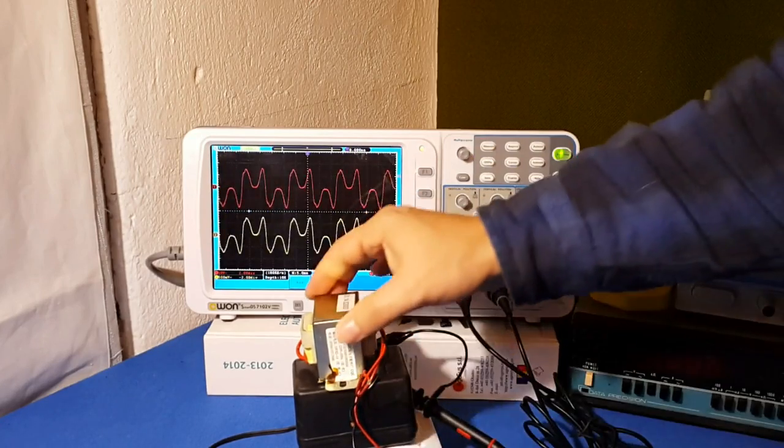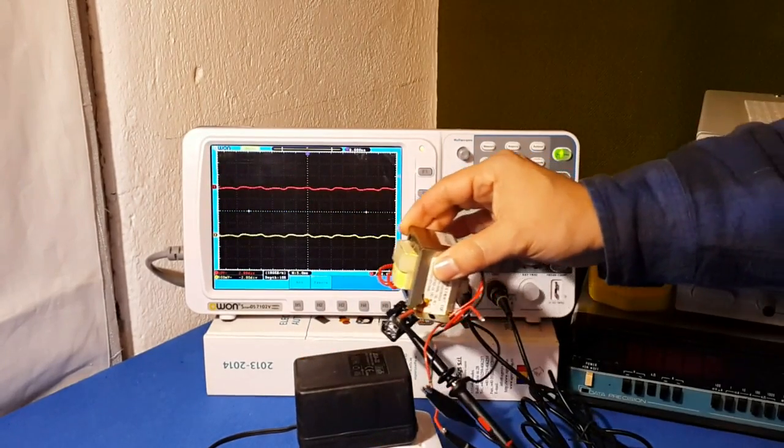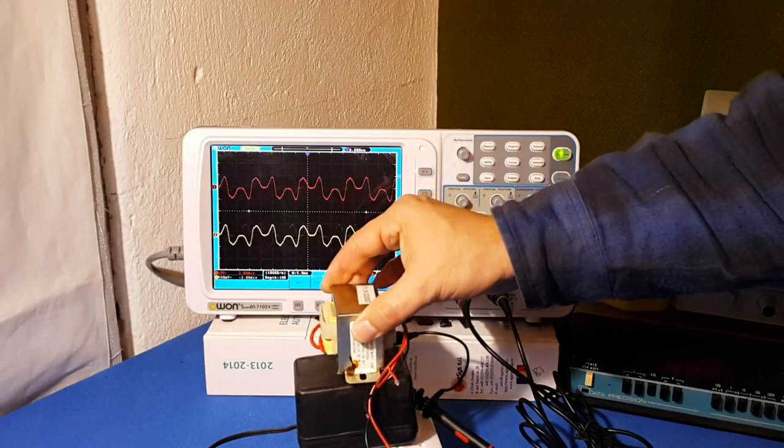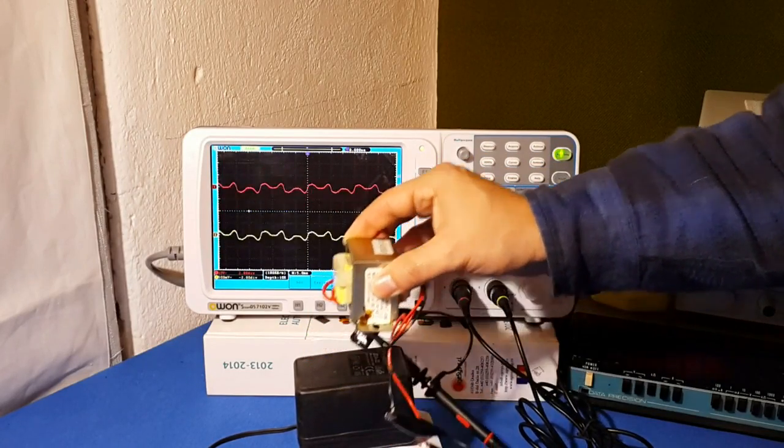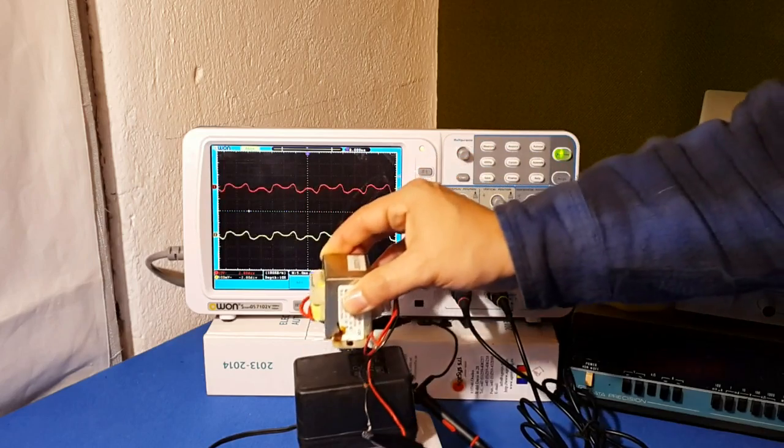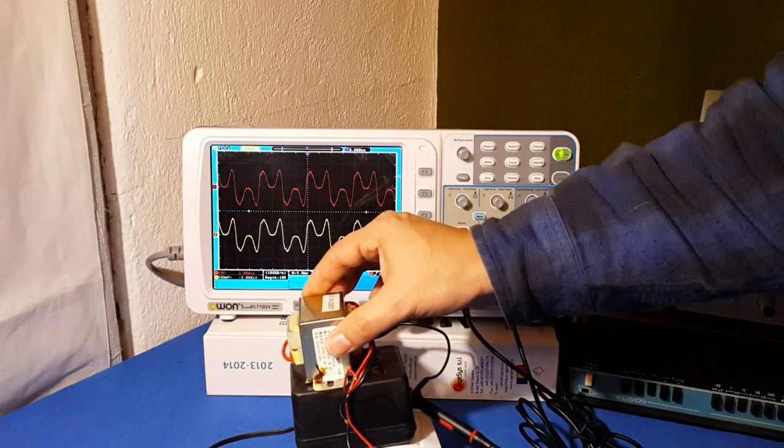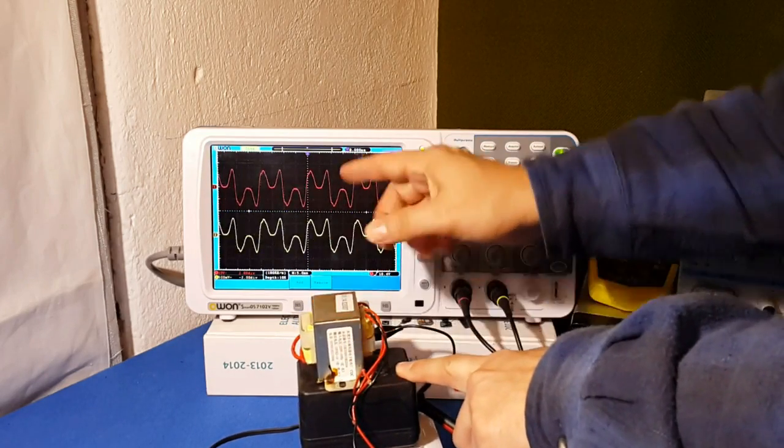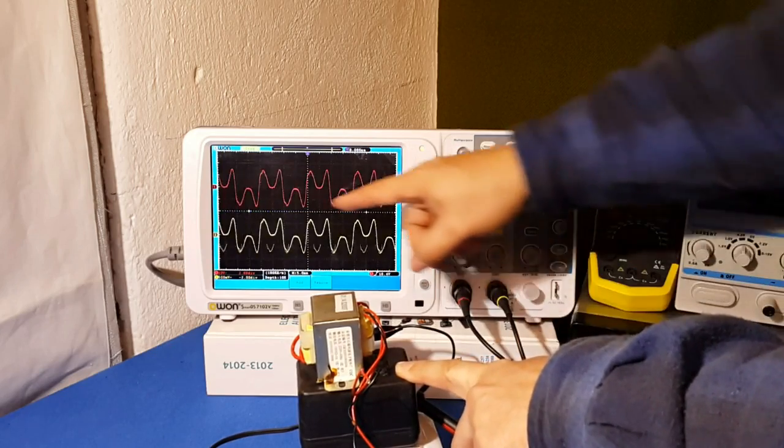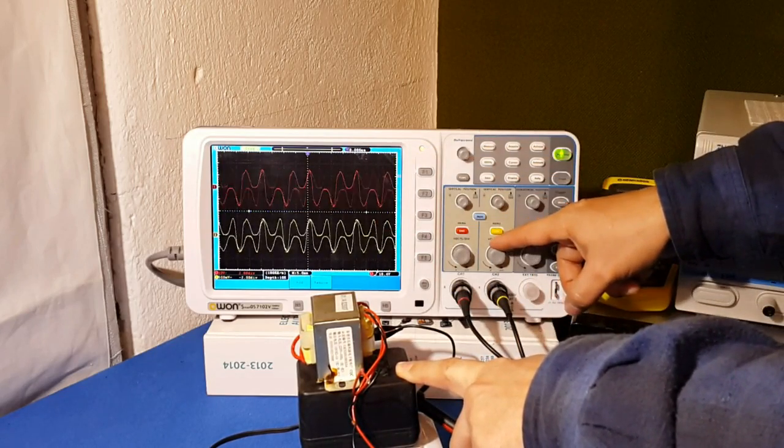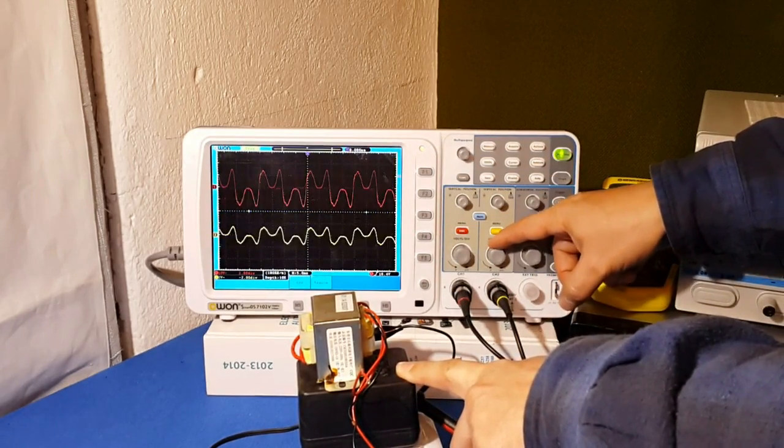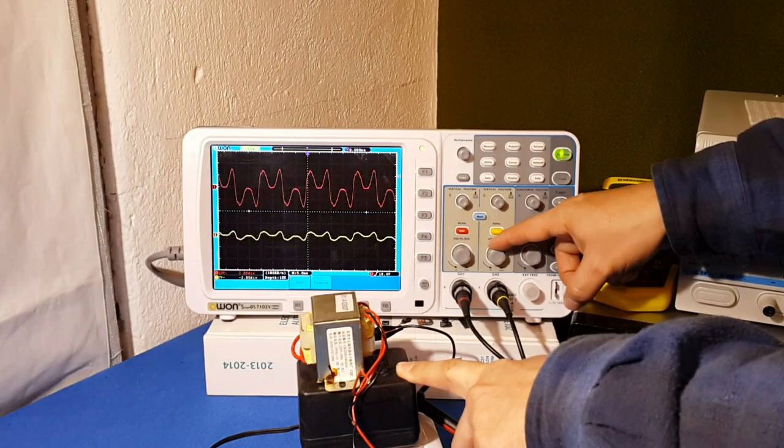So remember, with the oscilloscope and even with a digital multimeter, the voltage should increase as I get close to another transformer, and the difference between the primary and secondary should be the ratio we calculated in the beginning and we are expecting to get.